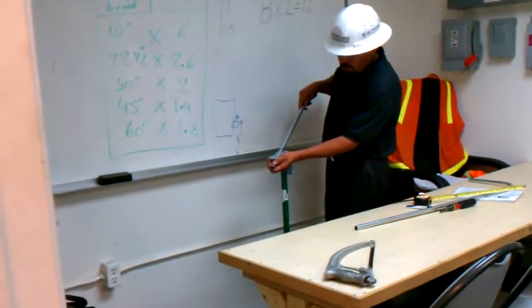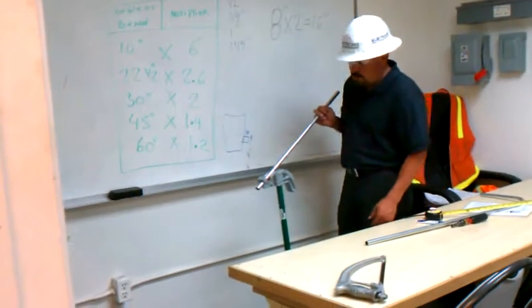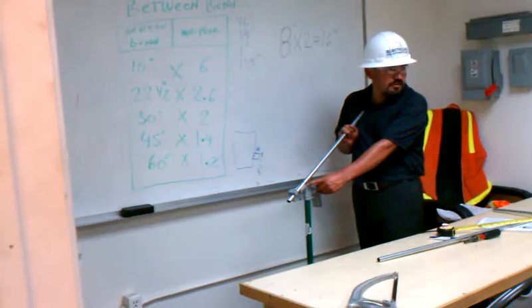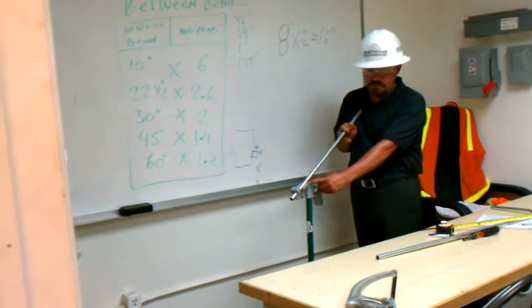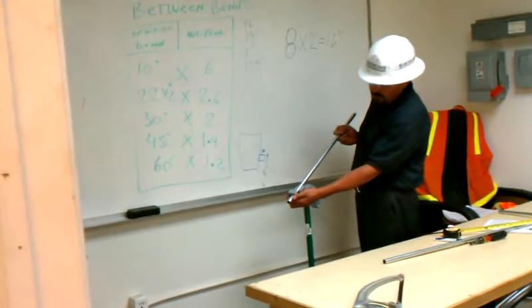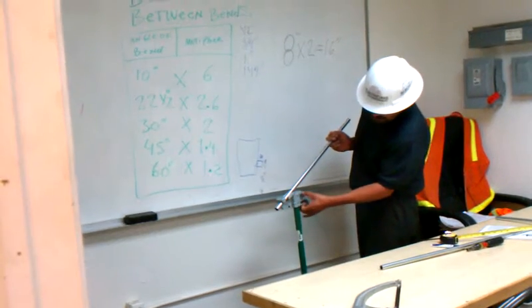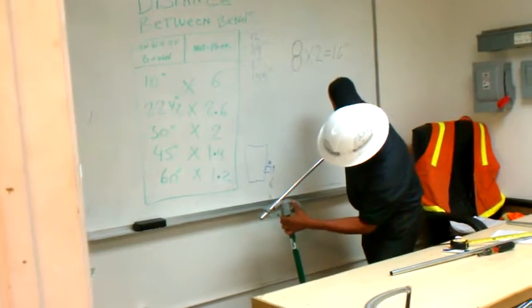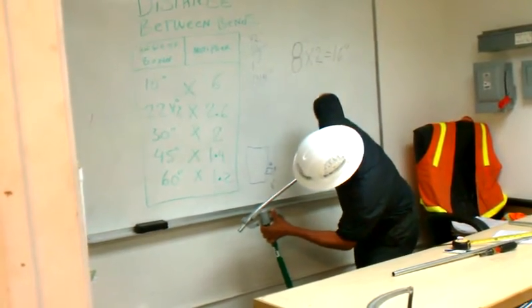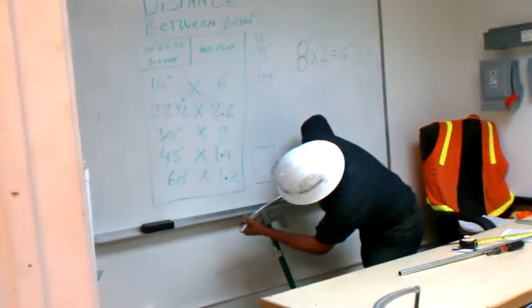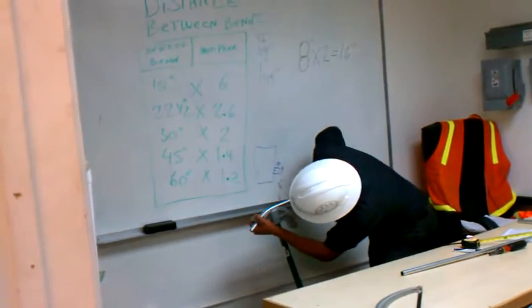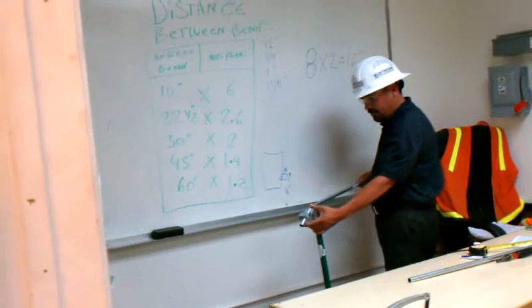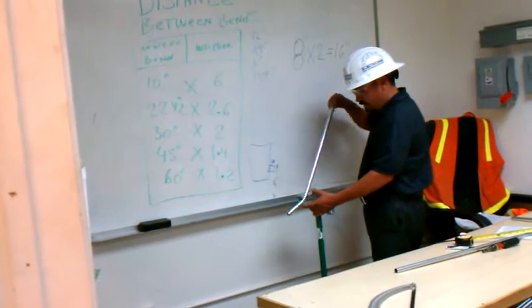Okay, so I want my bend to be right on the mark. So this is called the notch, or the center point. This is where I want my bend to be, so I have to get my mark there. And as you can see, we have the degrees here. We're going to go 30 degrees. So all you have to do is get it parallel to the 30 degrees. Okay, there it is - that's the 30 degrees right there.